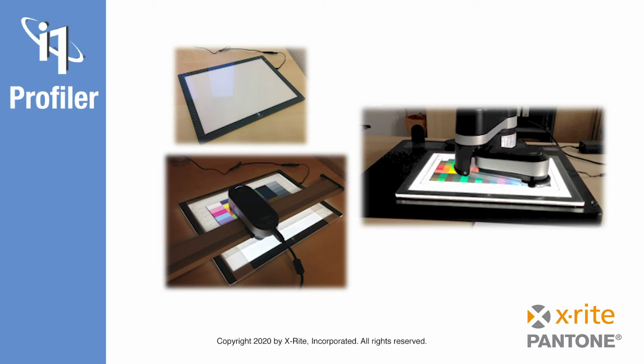For use with an i1-IO3 table, you should avoid light boxes with raised frames. This is because the i1-IO arm needs to glide smoothly over the entire light box.